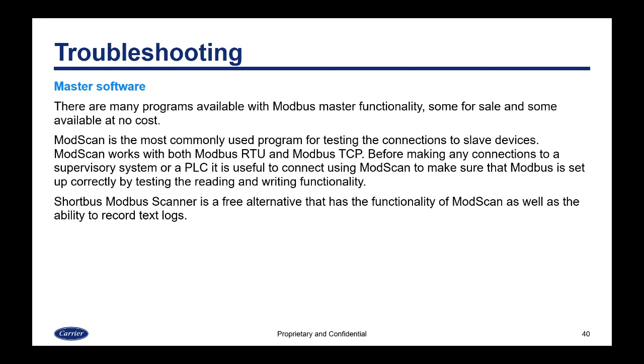Before making any connections to a supervisory system or a PLC, it is useful to connect using ModScan to make sure that Modbus is set up correctly on the device — that the address is correct, the baud rate is correct — and to test the read and write functionality. Shortbus Modbus Scanner is a free alternative that has the functionality of ModScan as well as the ability to record text logs.